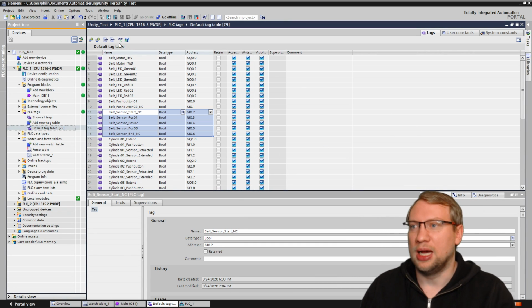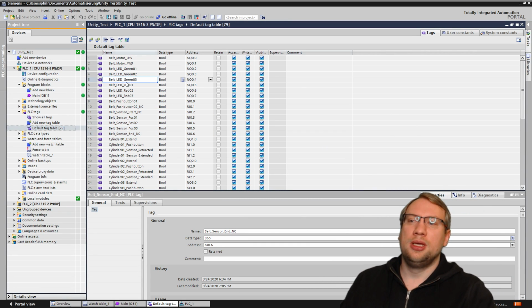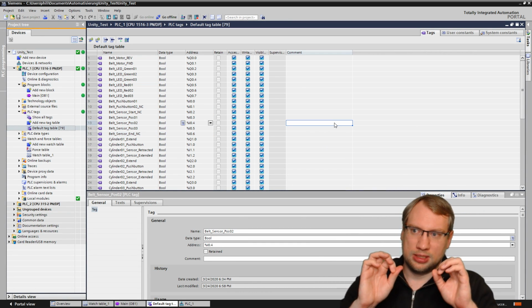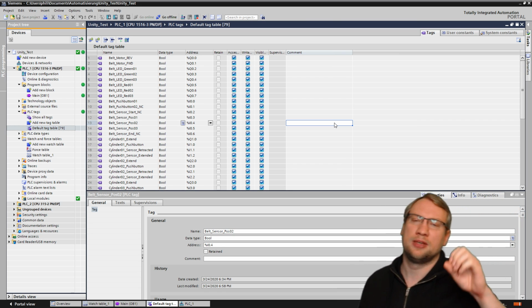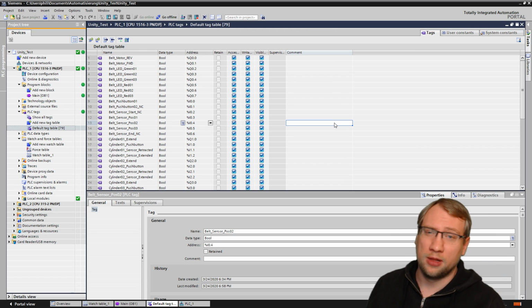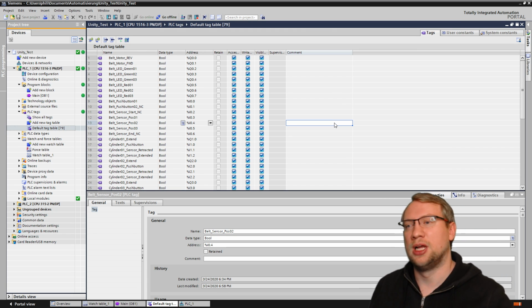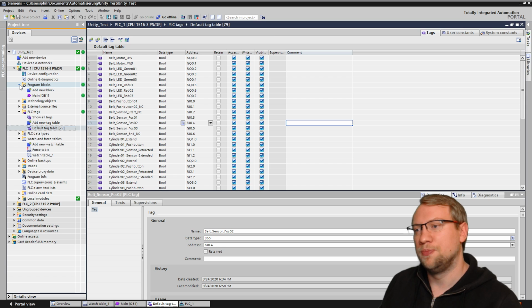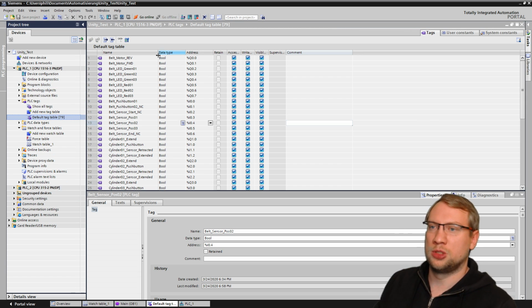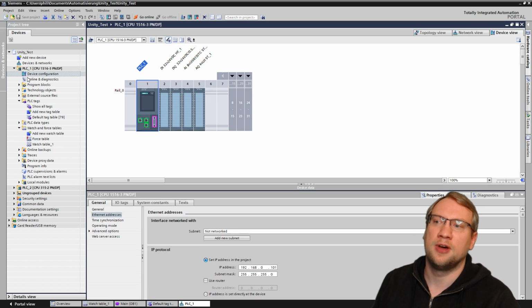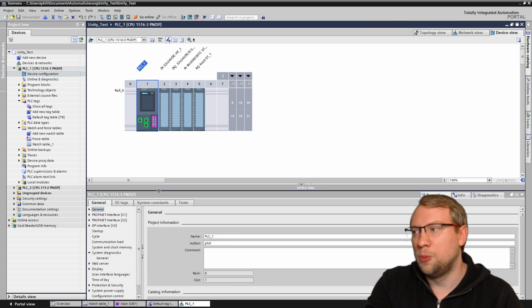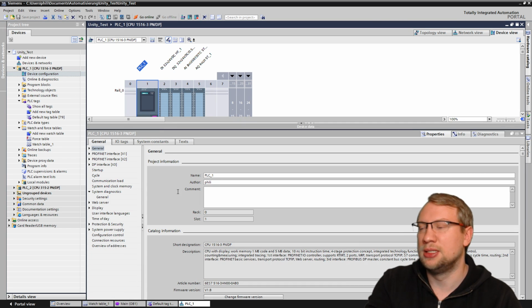So yeah, to actually set this up, there's a couple of things that need to be done. If you are working with an S7, if you want to work with an S7-1200 or 1500, because my tool works with Put/Get commands, you have to go to your device configuration and open up the settings down here.